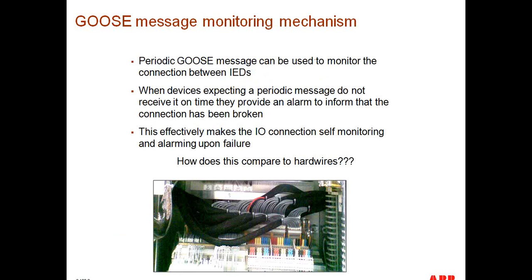Now, going back to these periodic messages, they can be used to monitor the connection between IEDs. When devices expecting a periodic message do not receive it on time, they provide an alarm to inform that the connection has been broken. This effectively makes the I/O connection self-monitoring and alarming upon failure. So when we take a look at this piece of switchgear that has multiple dozens of connections, how is this done here? How is this self-monitoring in this particular case?